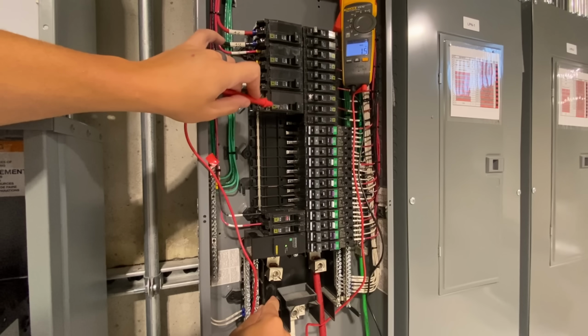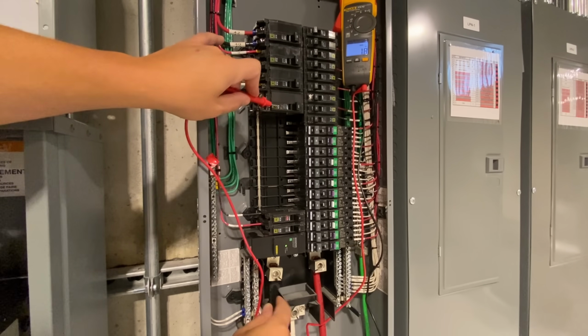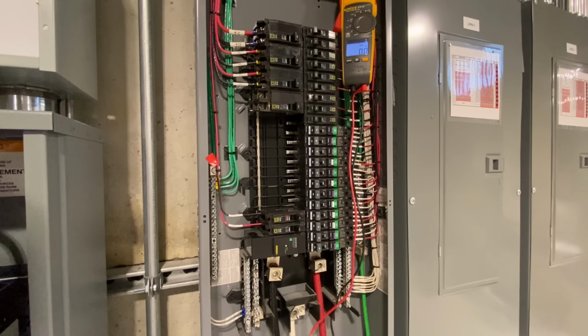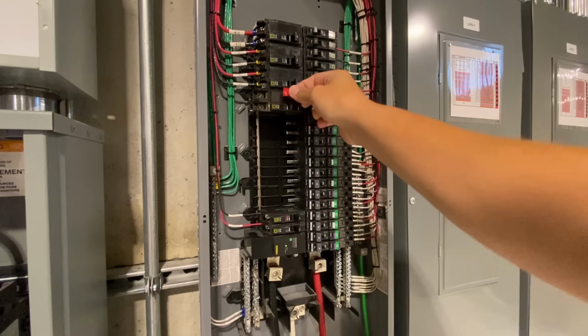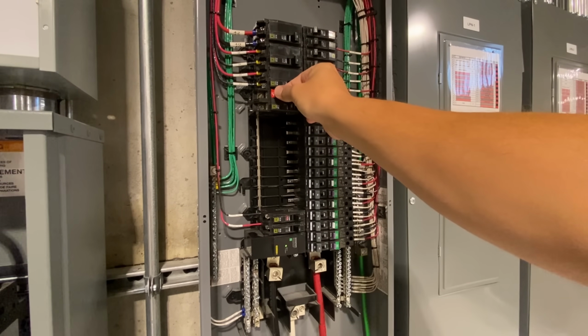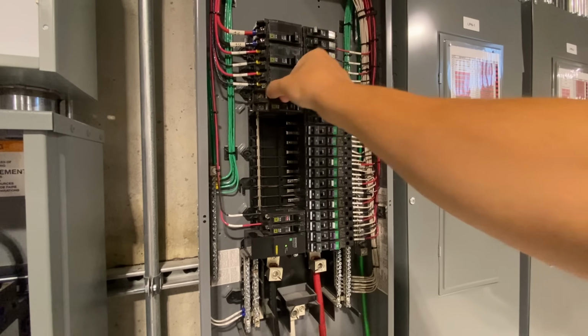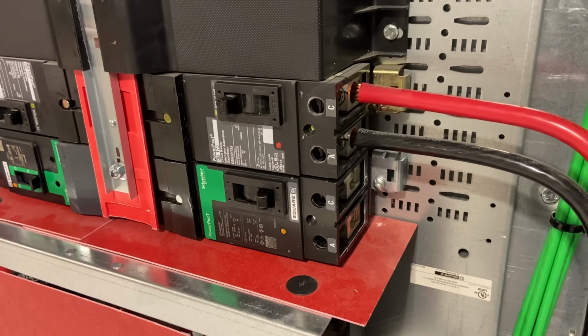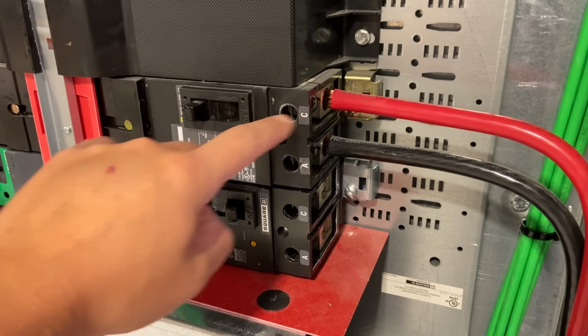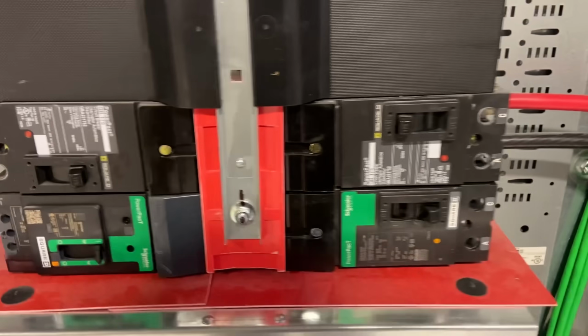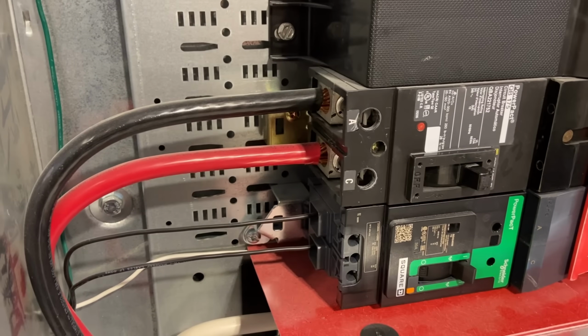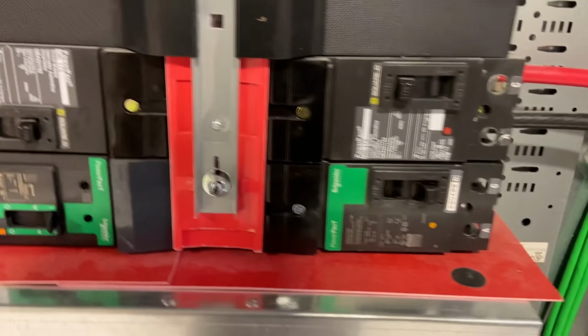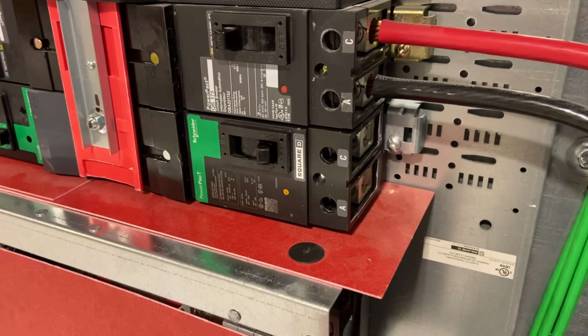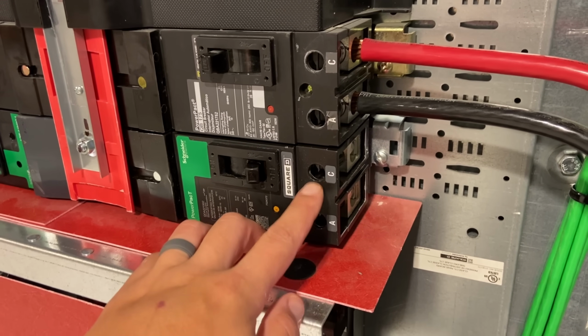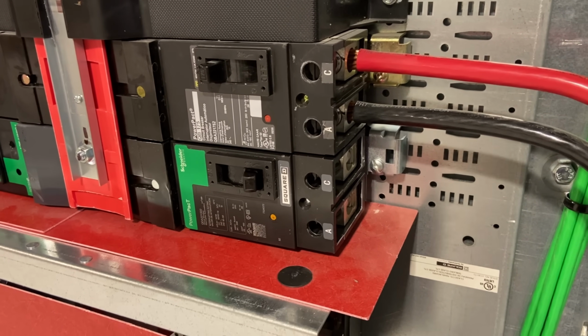So if you have 0 volts going from one phase to another, you're on the same phase. And if you have voltage, you're on an opposite phase. In this case, there's only one other. In three-phase, you don't know exactly which one you're going to, but you know it's not the same phase. Of course, that was kind of a stupid test because everything in that panel is actually already phased correctly. In the I-line panel, it's even easier because they actually just use letters, and we're using all A and C phase in this panel because in an I-line panel running on single phase, you only use the top and bottom bus bars.